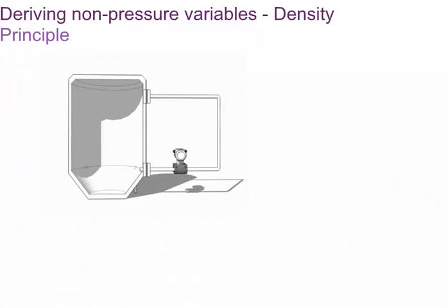The preceding method leads to density measurement in a tank. In this case, a homogeneous liquid of changing density in the tank will exert varying pressure on the transmitter depending on the change in density. This measure can be applied either in open or closed tanks and with clean or dirty fluids. As long as the level remains above the top tap, and as long as H is constant, the transmitter will respond to changes in density.